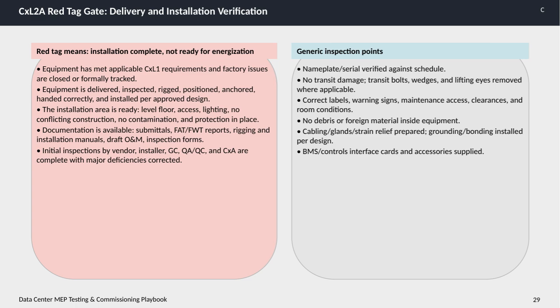Initial inspection should be completed by all relevant parties. This includes a vendor, installer, general contractor, quality assurance and quality control teams, and the commissioning authority. Major deficiencies found during these inspections must be corrected to ensure compliance. Some generic inspection points to keep in mind include verifying the nameplate and serial numbers against the schedule to ensure accuracy. The equipment must show no transit damage, and all transit bolts, wedges, and lifting eyes should be removed where applicable. We also need to confirm that the correct labels and warning signs are in place.